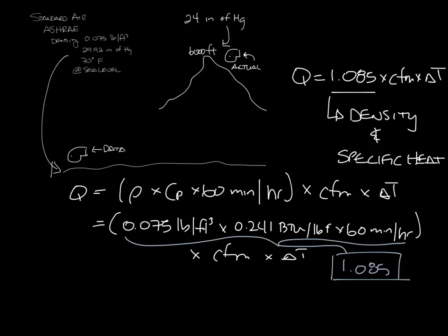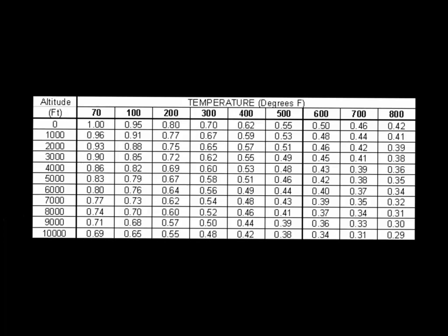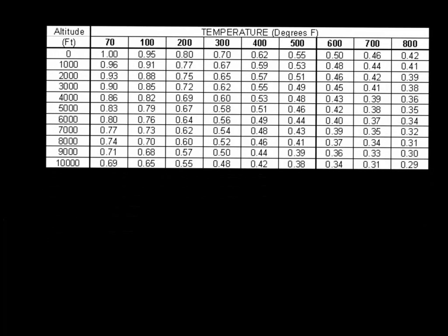Luckily you don't have to know the air density at every altitude and temperature. Lots of people have correction factor tables you can look at. So let's move this over here. And here's an example of a correction factor table by altitude and by temperature. Let's move this up and give myself some room. So you can see at 6,000 feet and 70 degrees, the correction factor is 0.8. So you take your 1.085 times your 0.8 and that gives you 0.87.